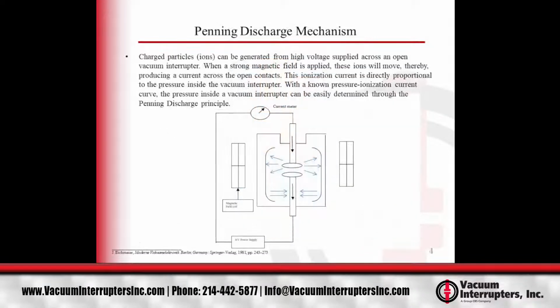So the way that vacuum interrupters are tested is what's called a Penning discharge mechanism. Penning was a scientist who found this effect where if you apply a high voltage and a magnetic field, then you can create a current that is proportional to the pressure inside of the volume. So the higher the pressure inside of the vacuum interrupter, the higher the current that you're going to measure. This is the basis of our MAC test set.